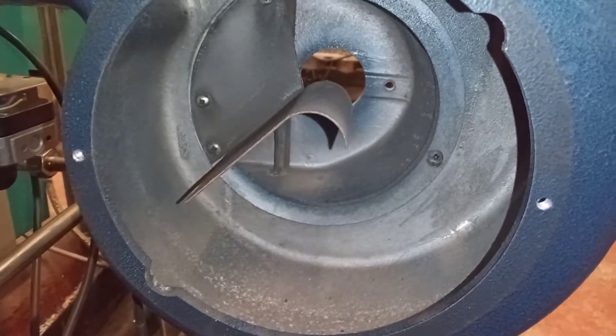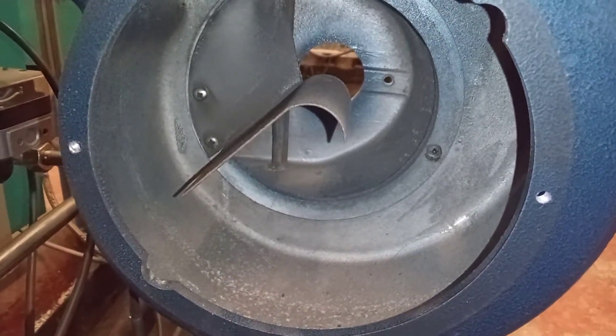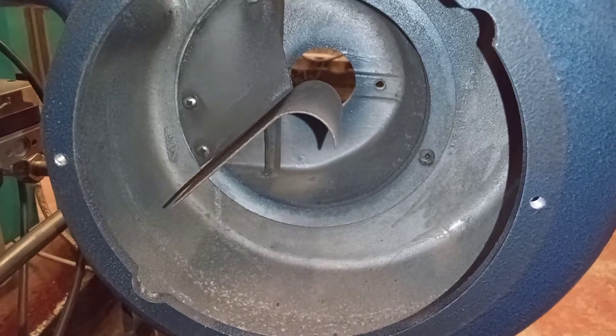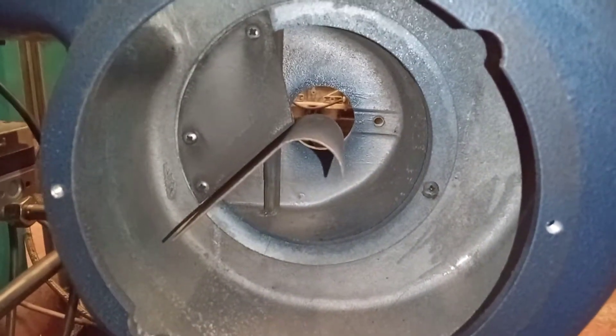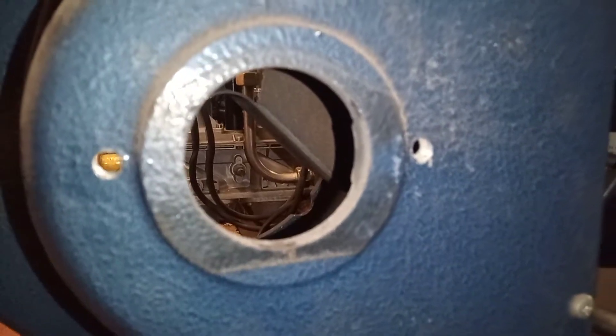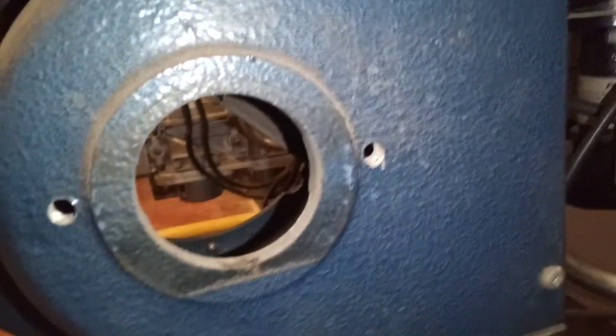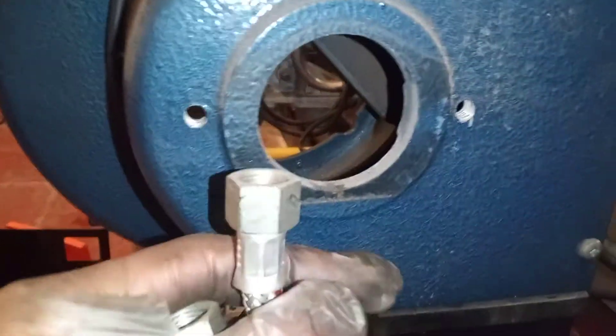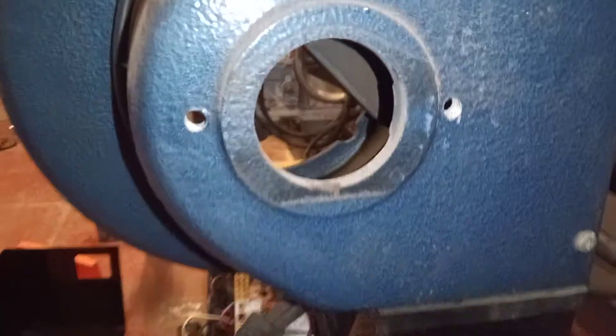So that's why the boiler was locking out. Here's a look inside from this angle at where the fan motor sits — do check out my other video on changing the fan motor if you haven't seen it. This is the other side where the oil pump is. I've got all our oil isolated and disconnected all connections from the oil pump.